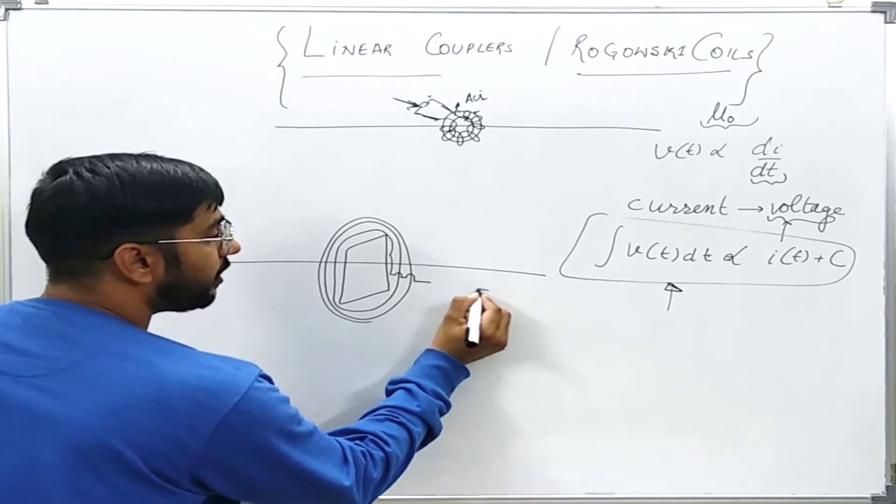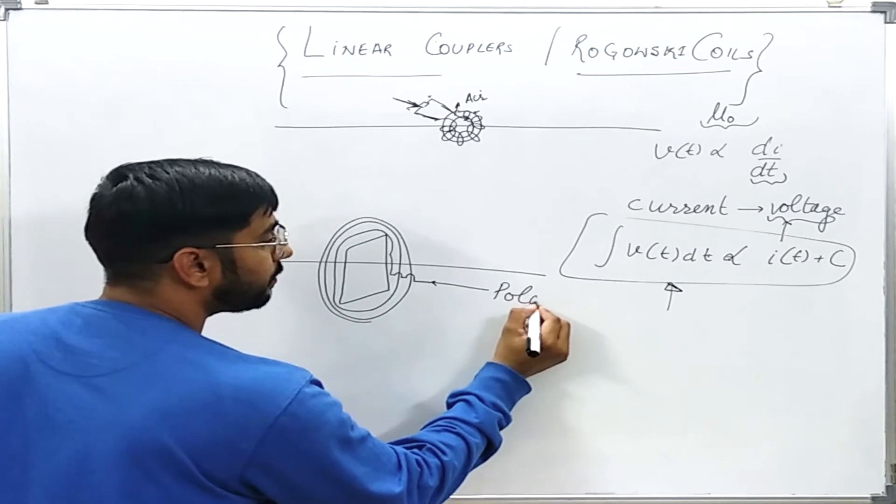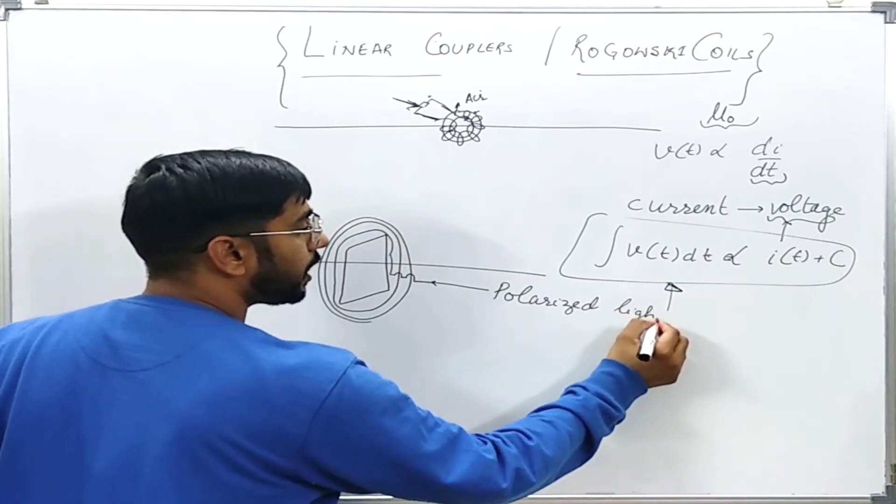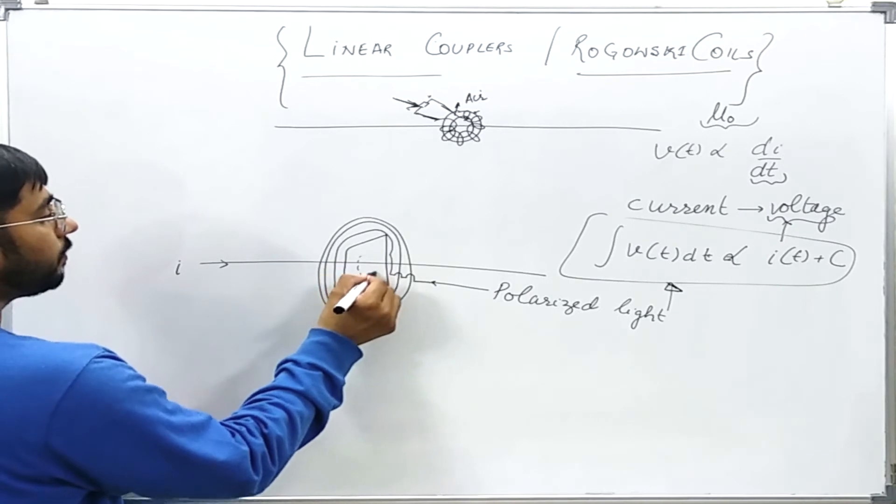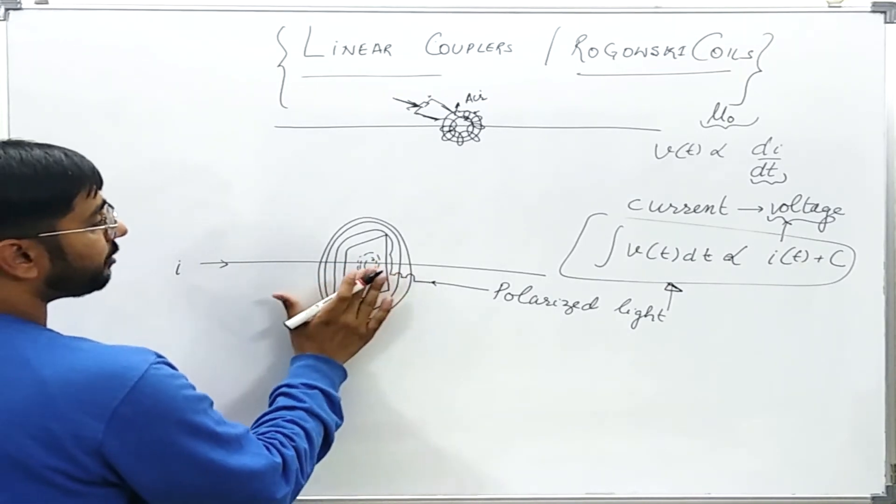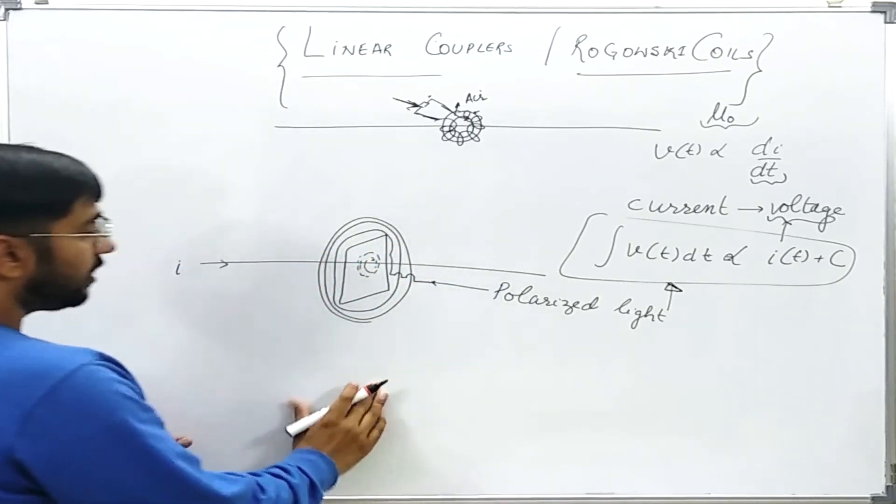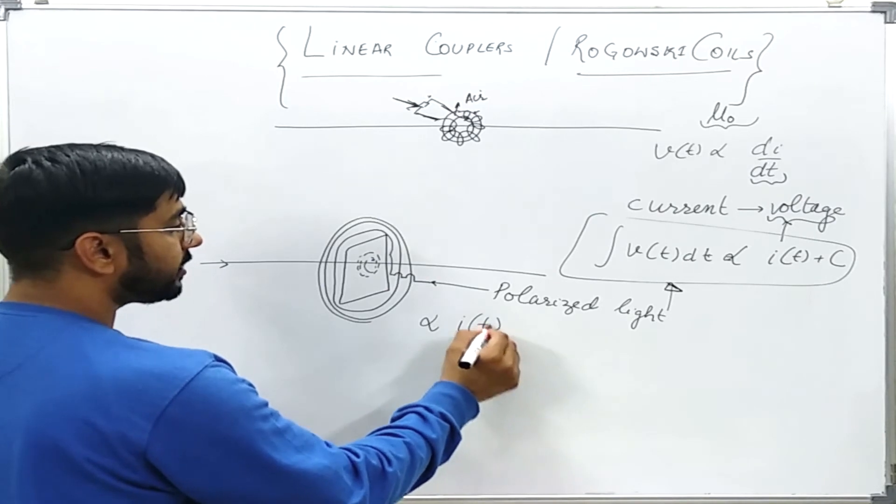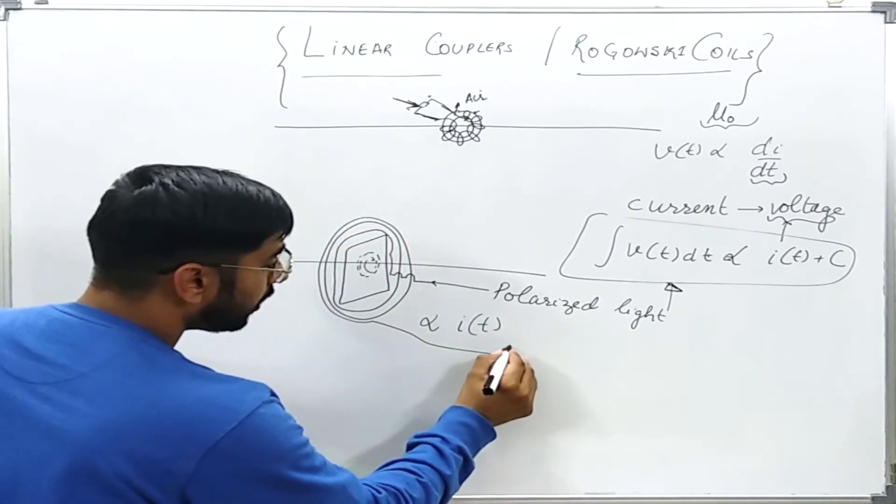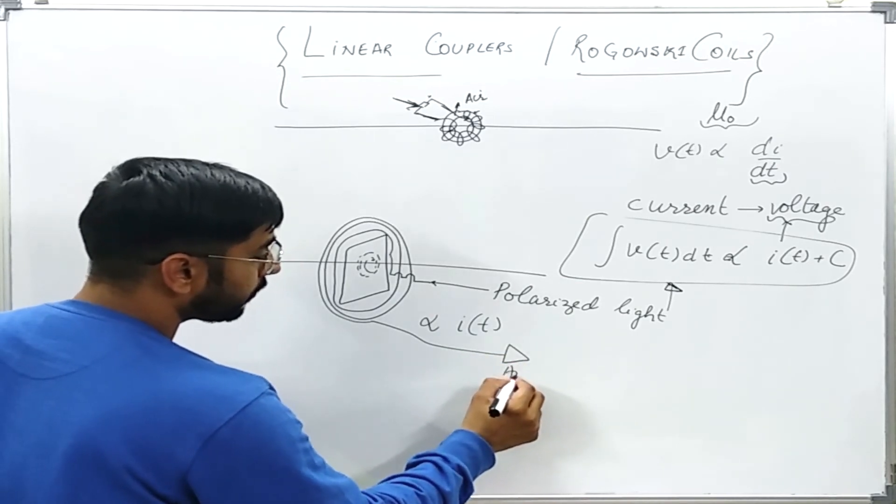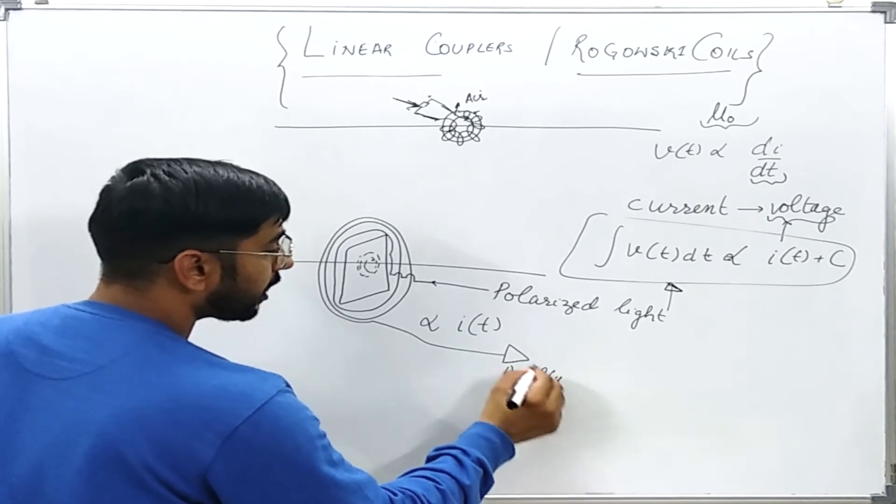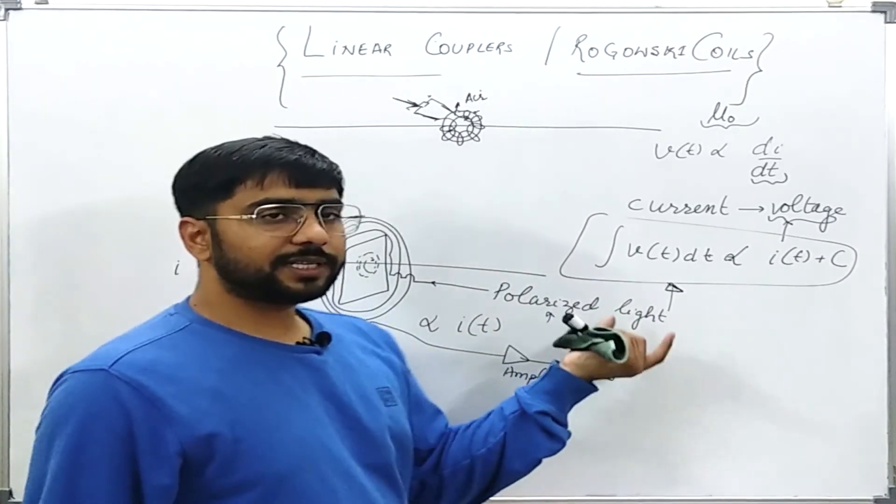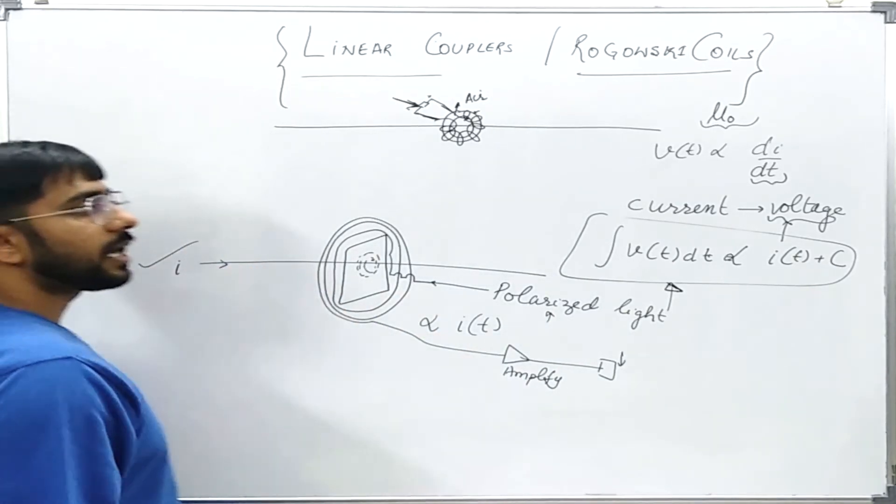From here I will input a light signal which is already polarized to some given angle - polarized light I will input. This current is going to create magnetic field. This magnetic field is going to shift the polarization angle or the plane of the polarization. This shifting will be proportional to the instantaneous value of the current in this conductor. What I will do? I will take this signal, amplify it, and compare the phase angle of the polarization of the input and the output. Based on this difference I can easily find the instantaneous value of the current in the primary.